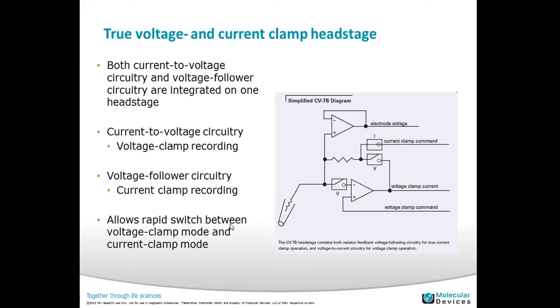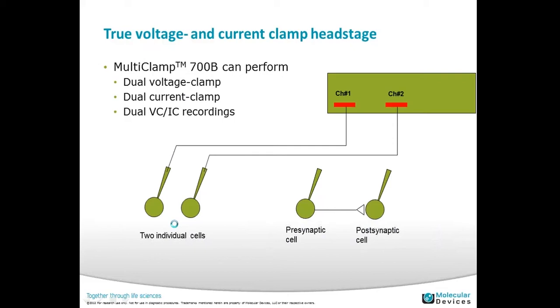Now, in the 700B head stage, called the CV7B head stage, it contains two circuitries in one head stage. We have the current to voltage circuitry, that's for voltage clamp recording, and the voltage follower circuitry, that's for current clamp recording. We integrated them in one head stage so it allows a rapid switch between voltage clamp mode and current clamp mode.